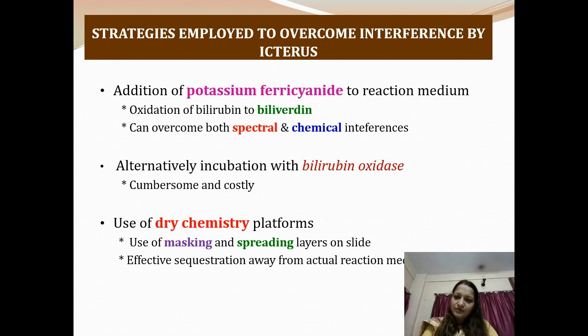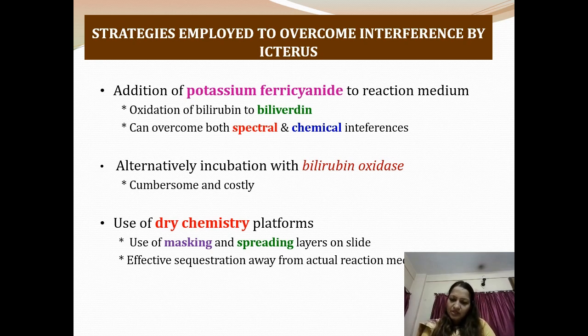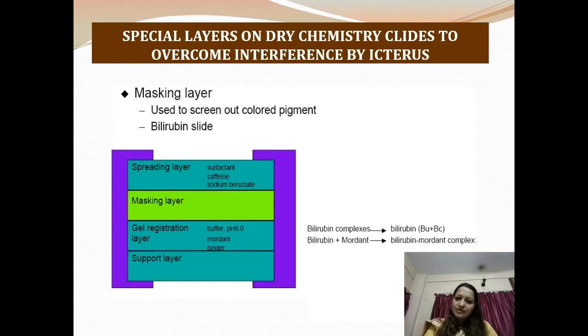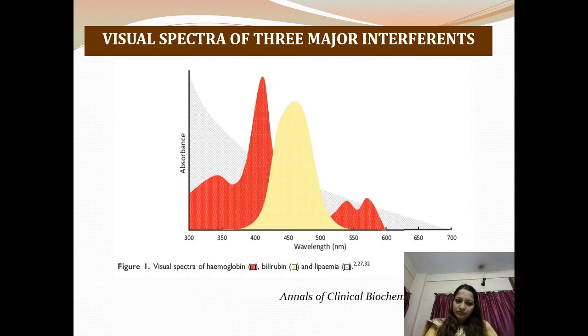Strategies to overcome interference by icterus include: addition of potassium ferricyanide to the reaction medium, which as an oxidizing agent oxidizes bilirubin to biliverdin, overcoming both spectral and chemical interference. Alternatively, the sample can be incubated with bilirubin oxidase, which achieves the same purpose but is cumbersome and costly. Use of dry chemistry platforms with a masking and spreading layer sequesters bilirubin away from the actual reaction medium — a very good alternative. Special layers on dry chemistry slides overcome the interference by icterus. A visual spectrum chart shows the absorption profiles of the three major interferents: hemoglobin, chylomicrons, and bilirubin.